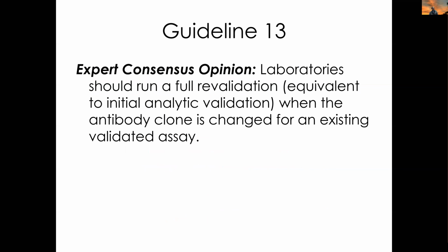And then guideline 13, again, expert opinion, laboratories should run a full revalidation when the antibody clone is changed for an existing validated assay. So that's the most significant change you can make in your assay function, and revalidating entirely with a new clone is what's involved.